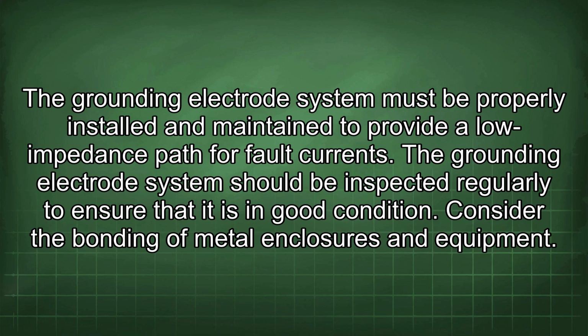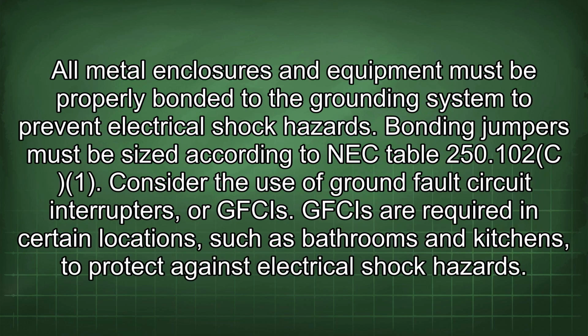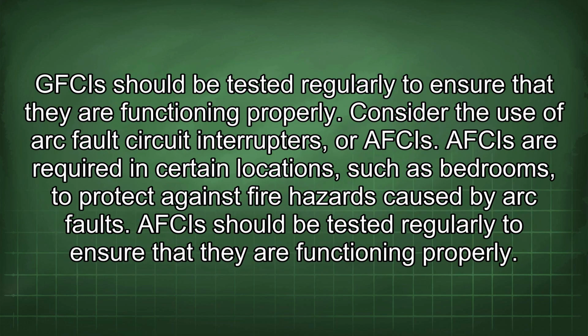Consider the bonding of metal enclosures and equipment. All metal enclosures and equipment must be properly bonded to the grounding system to prevent electrical shock hazards. Bonding jumpers must be sized according to NEC Table 250.102(C)(1). Consider the use of ground fault circuit interrupters, or GFCIs. GFCIs are required in certain locations, such as bathrooms and kitchens, to protect against electrical shock hazards. GFCIs should be tested regularly to ensure that they are functioning properly.